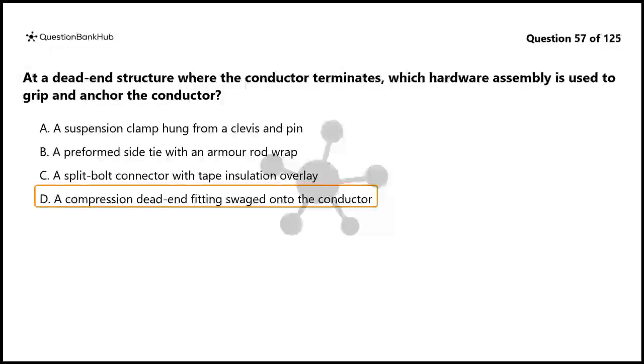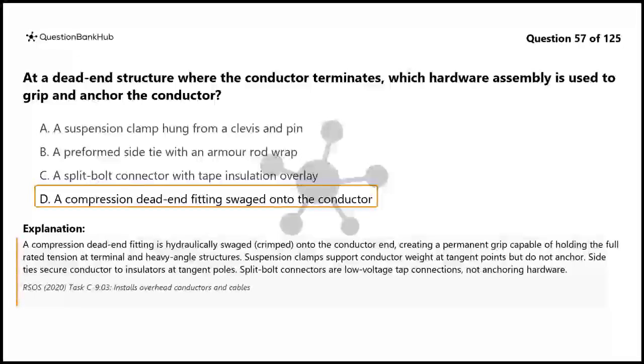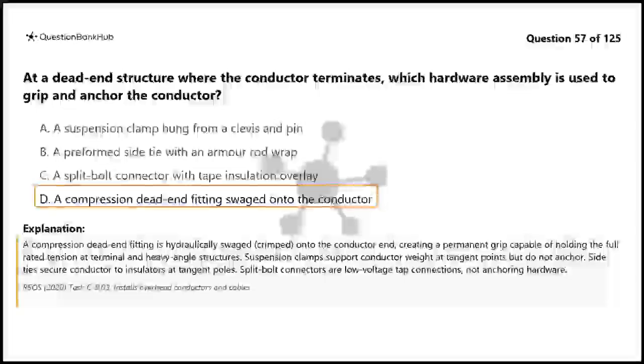The correct answer is D. A compression dead-end fitting is hydraulically swaged, or crimped, onto the conductor end, creating a permanent grip capable of holding the full rated tension at terminal and heavy angle structures. Suspension clamps support conductor weight at tangent points but do not anchor. Side ties secure conductor to insulators at tangent poles. Split bolt connectors are low-voltage tap connections, not anchoring hardware.